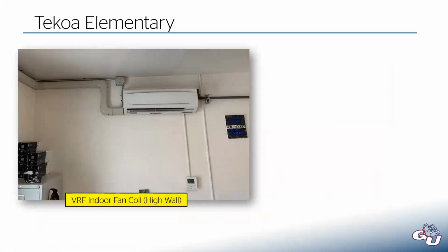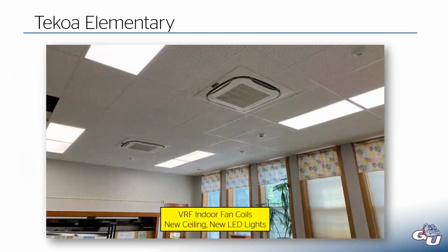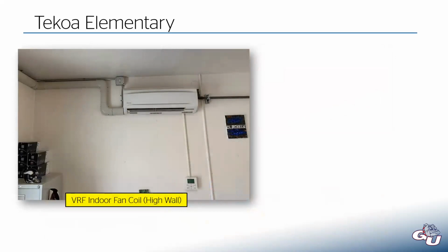Another style of VRF fan coil is what we call a high wall unit. And so this would be used in a room where we don't install the ceiling. So these previous units, like I said, they stick above that ceiling about 12 inches. So you need some room to mount these things. You need some headspace to do that. If you don't have a ceiling, in this case, this was the principal's office, and it was in kind of an unusual location in the building. And to this hard lid ceiling right here was only about 8 feet, which is pretty low for a ceiling. And so if we were to try to drop that another foot by putting in a new ceiling, that would really start to constrain the feeling of that room.